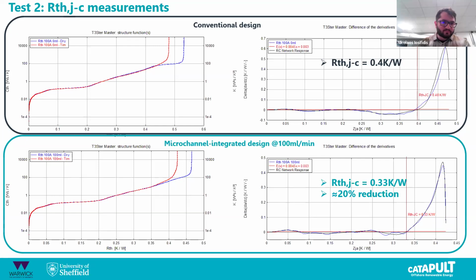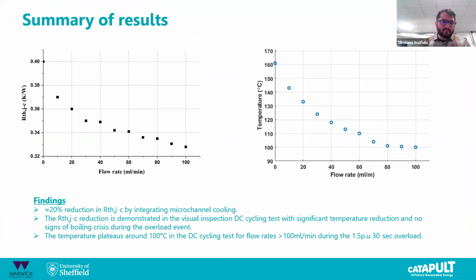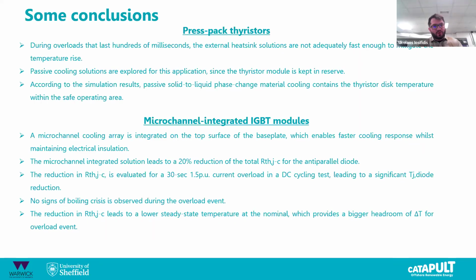And next slide, please. So the summary of the results is, by using microchannels in this design, we can reduce the RTH for the diode by 20%. And this is demonstrated by a visual inspection of the DC cycling test to ensure that we don't have any instabilities there. And we can see that the temperature plateaus at 100 degrees C during this overload test during DC cycling. Next slide. So some conclusions: for press pack thyristors, since they're used only in reserve, we propose a passive cooling solution with phase change material cooling, which is also an electrical conductor.